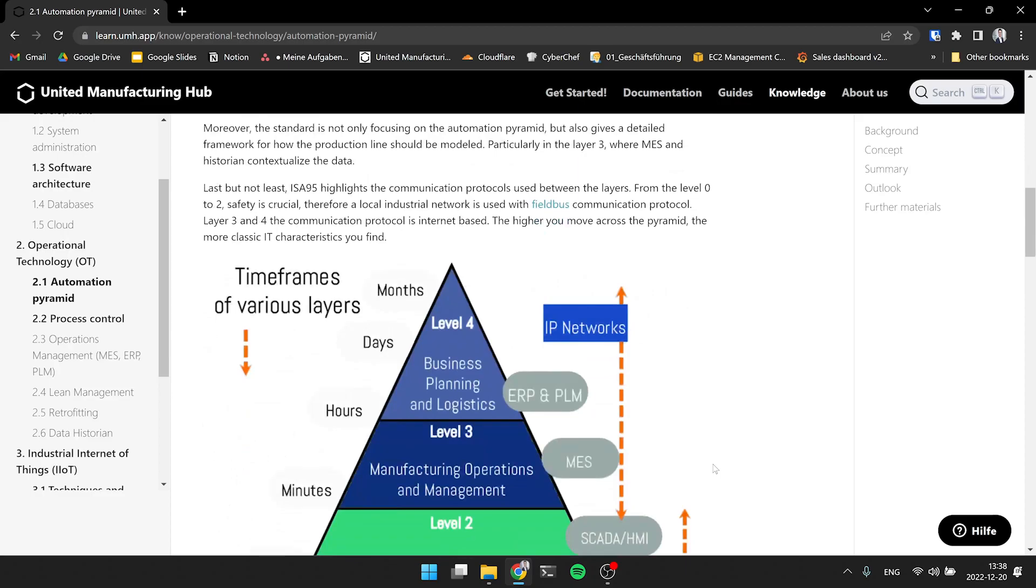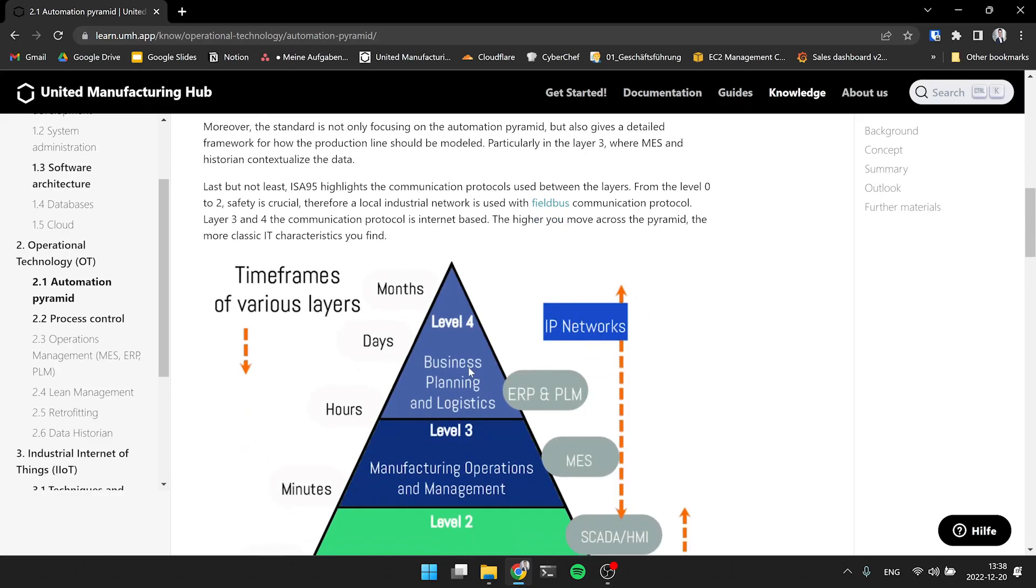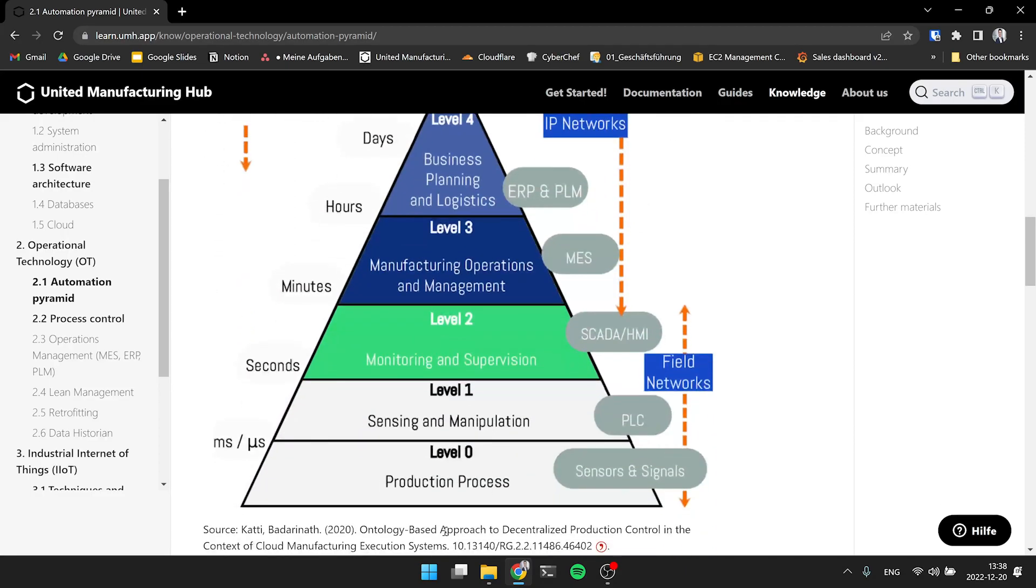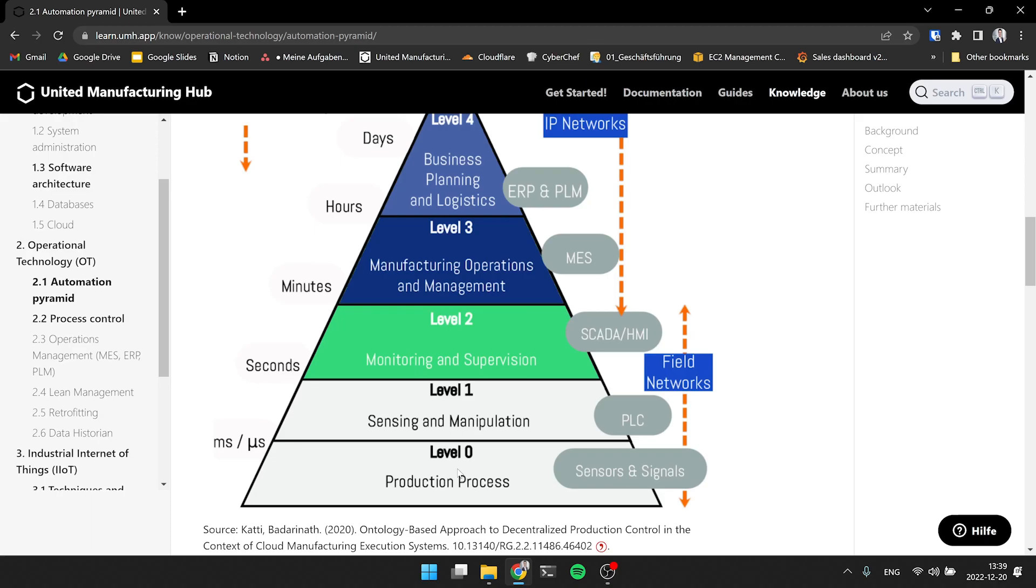Let's take a look at the bottom level. At the bottom, you always have the sensors and then at the next level you have the PLCs. We will later go into detail what PLCs are, but for now these are small computing units that take data from the sensors and then do very small controlling of the machines. Then the level above is the monitoring supervision system, like a SCADA system that looks at multiple PLCs and tries to ensure that they can communicate with each other. So if you have a process that spans 50, 100 meters, you typically have every five meters or so a PLC with all the sensors connected and then you have a SCADA system for the entire line.